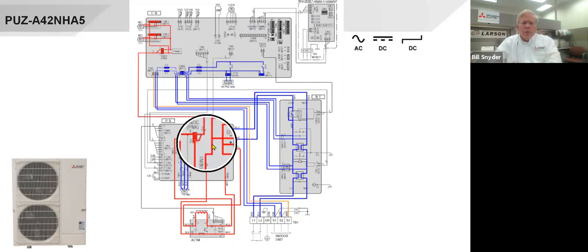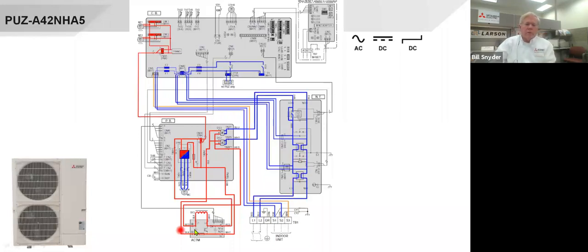So we're coming out of here with about 300 volts DC. In this case, we're also cleaning this up right here. This is one of those reactors. So we're running the DC voltage through the reactor. Sometimes we do the AC, sometimes we do the DC. In this case, these are little reactors here, so we've got reactors on both sides of this. For some reason, they felt they had to clean up that DC signal. The engineers did.